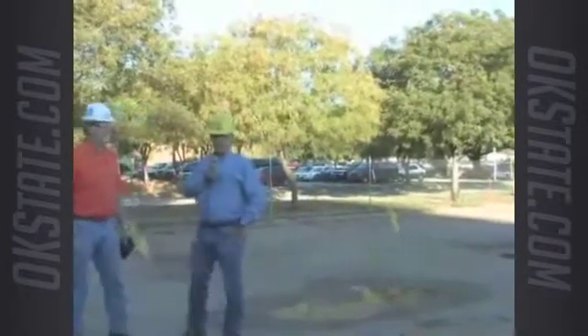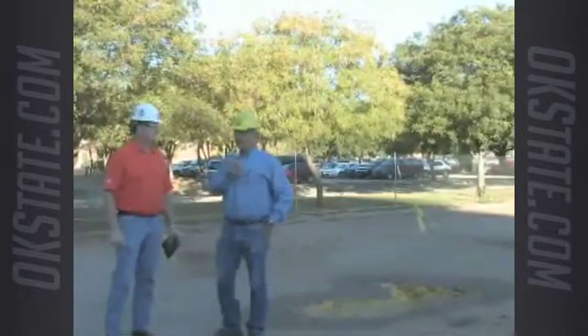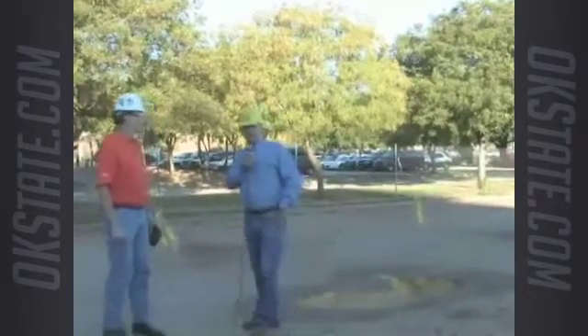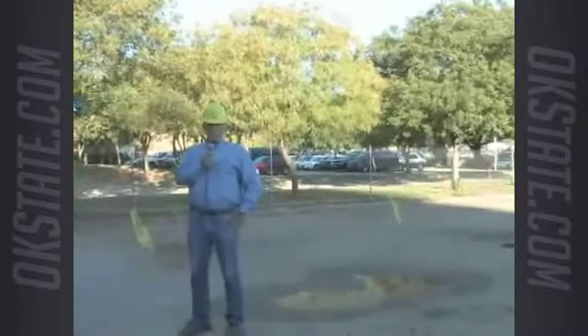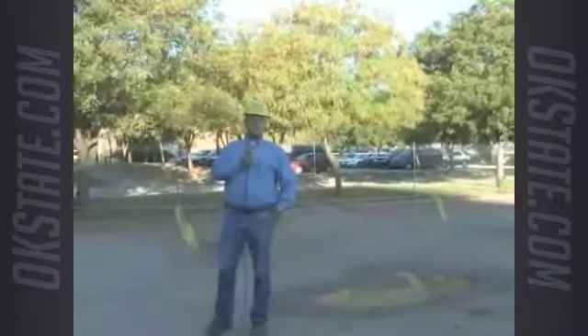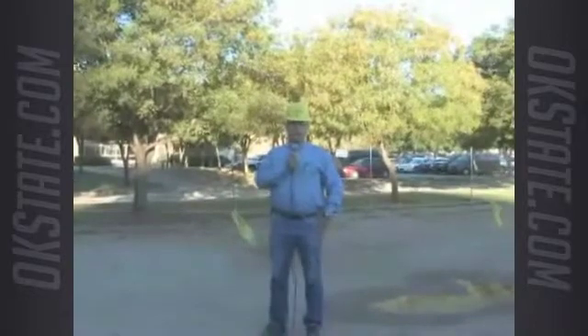Thank you, Jim. First of all, it's a pleasure to be on a project of this importance. Like you said, this is going to be the location of the 3 transformers that are fed from dual feeds from the university. This will be medium voltage, 13,200 volt coming to this location, and then it'll feed into 3 transformers where it's broken down into 480 volt.